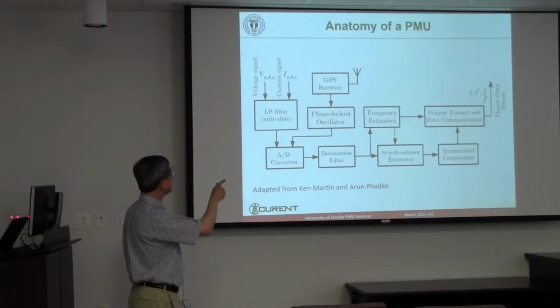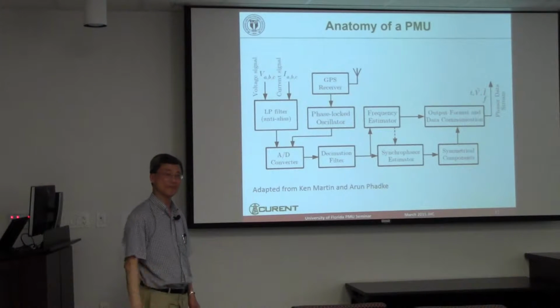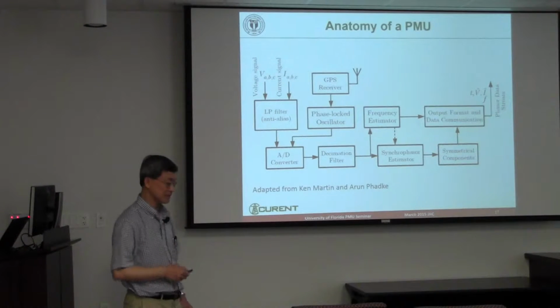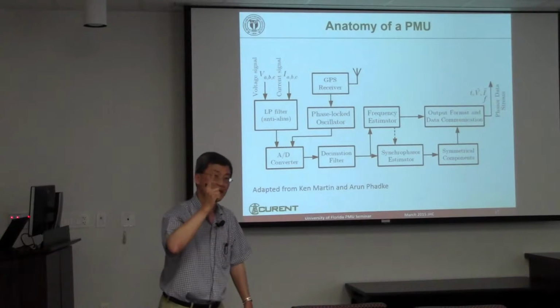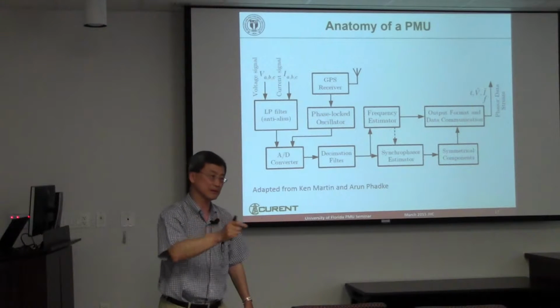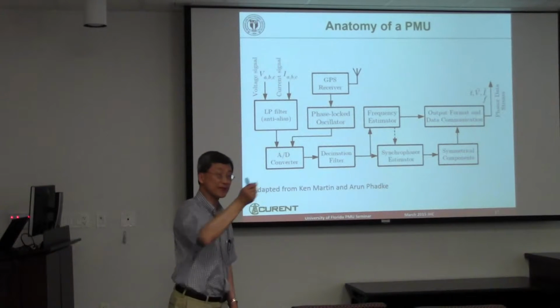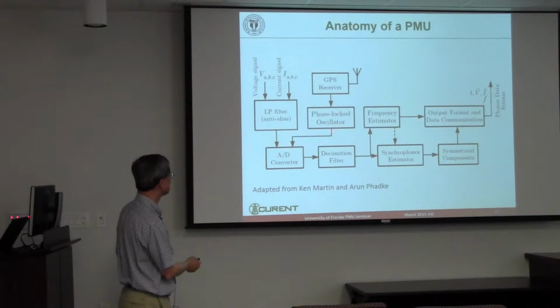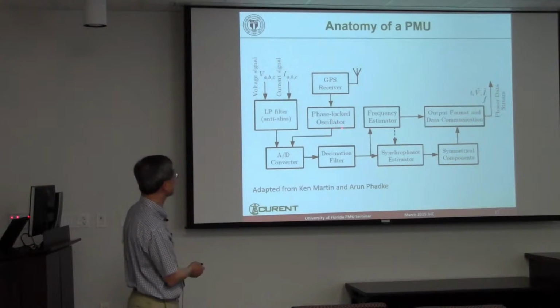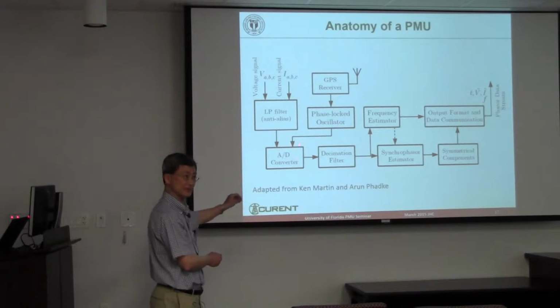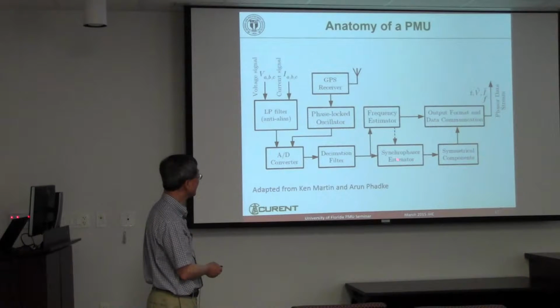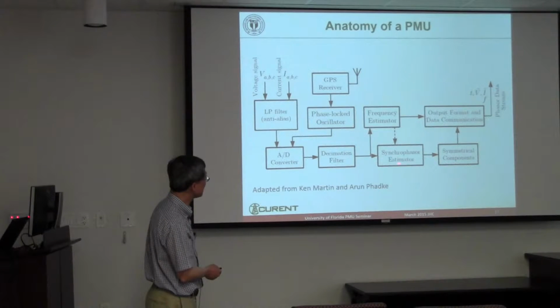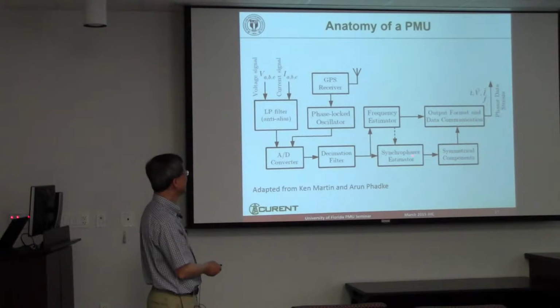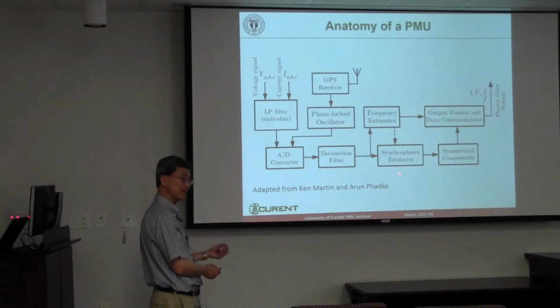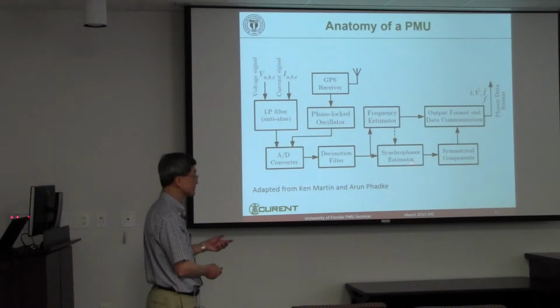This GPS signal, in the US, is about 0.2 microsecond in accuracy. GPS will put out a pulse every second, on the second. All these antennas do is pick up that second, and then it uses a phase lock loop type of oscillator to generate all the sub-second points for the A to D to do the sampling. So you have a decimation filter, and then a synchrophasor estimator, basically the FFT stuff. And then you can do a symmetrical component, because you have phase A, phase B, and phase C. Most PMUs measure all three phases.